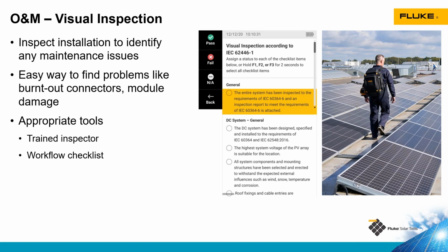It helps to have an inspector who is properly trained and knows what to look for. And the use of workflow checklists makes it easier for them to ensure that they don't miss anything as they're doing this visual inspection. That IEC standard we talked about has a large list of visual inspection items that need to be checked when we're doing our testing on our system. Those items are all included in a list in the SMFT 1000, which is what we see here in the middle of the screen. Each one of the items in that IEC standard are in there, and you can easily hit pass, fail, or not applicable, and save that data in the tool, and then export it to a computer later where you can create a very easy report to meet those IEC standards.